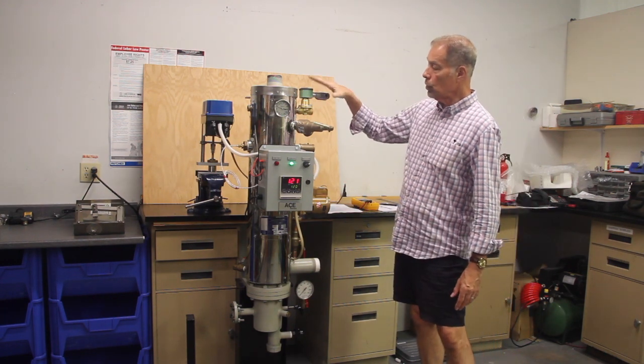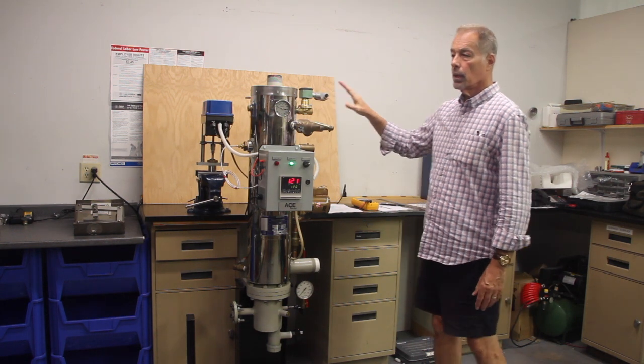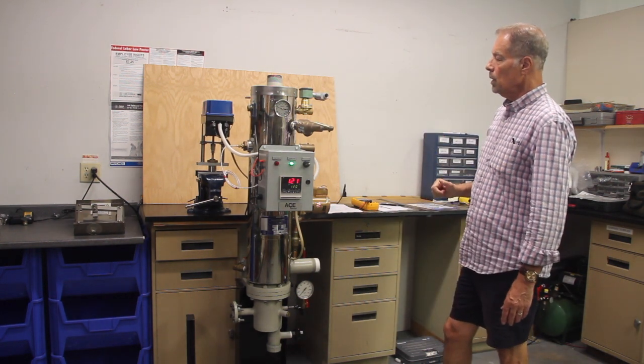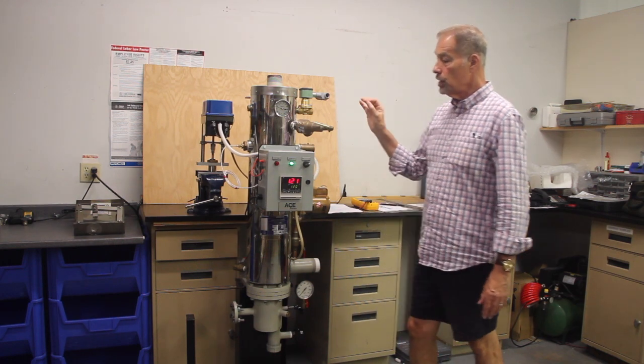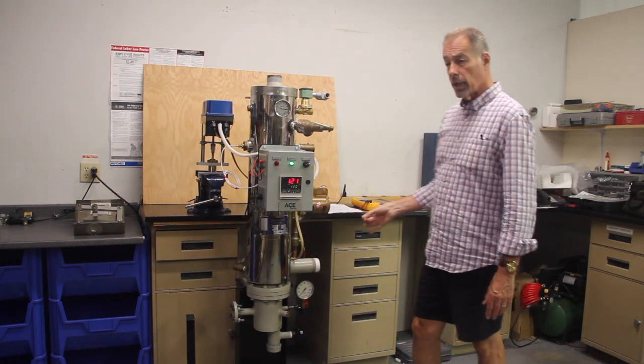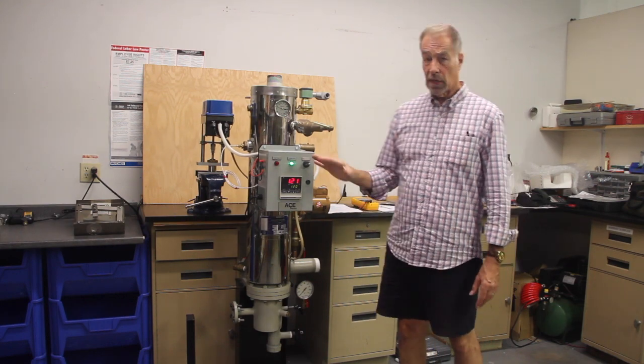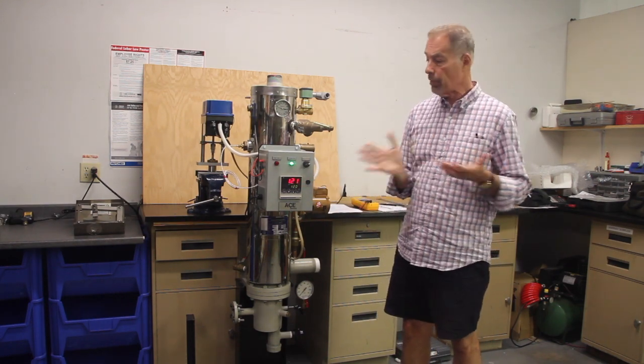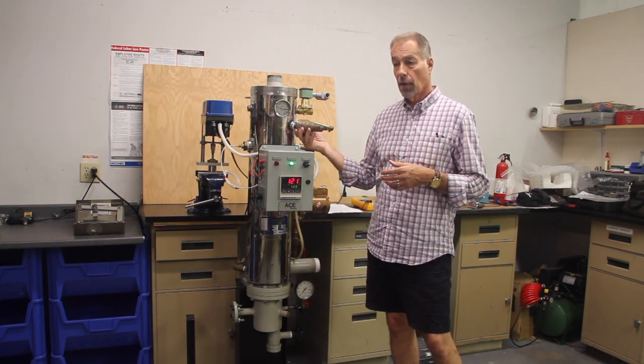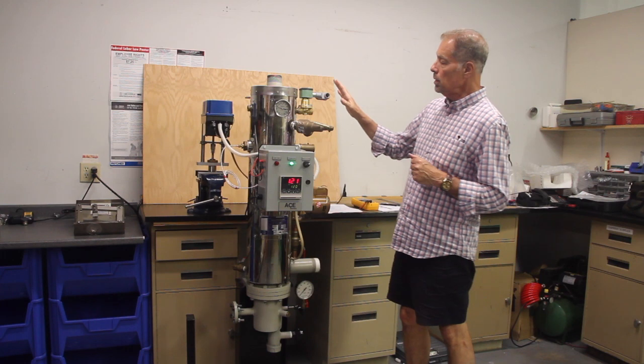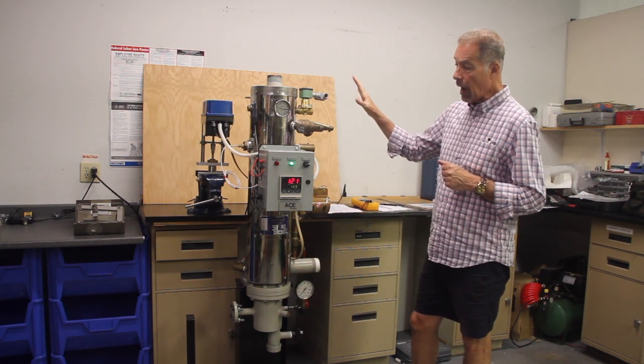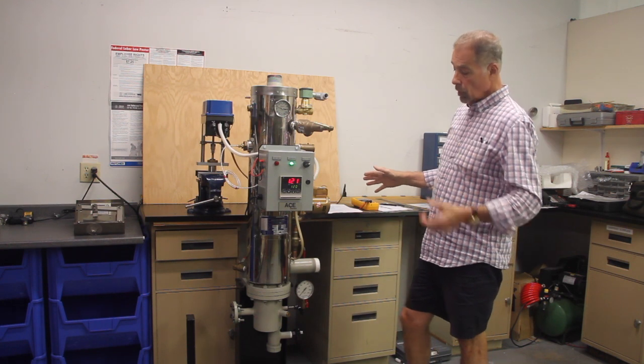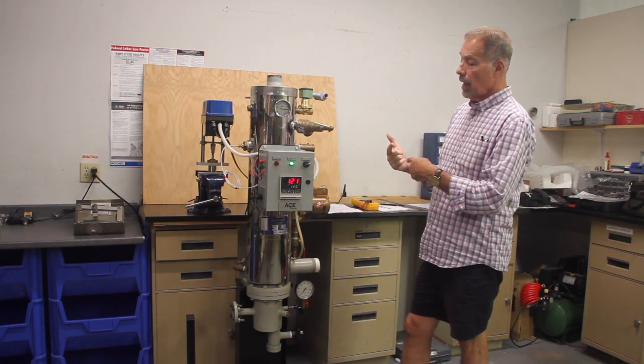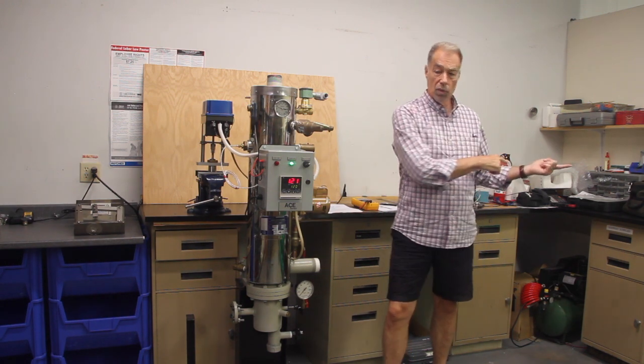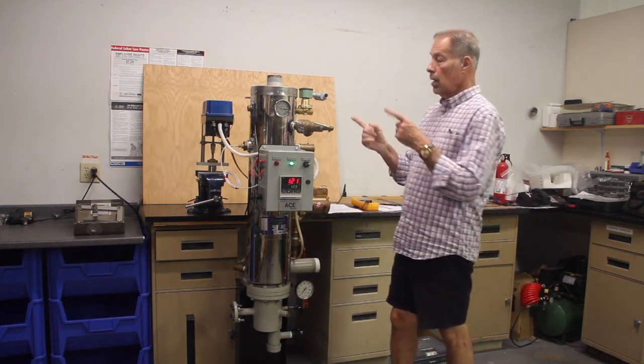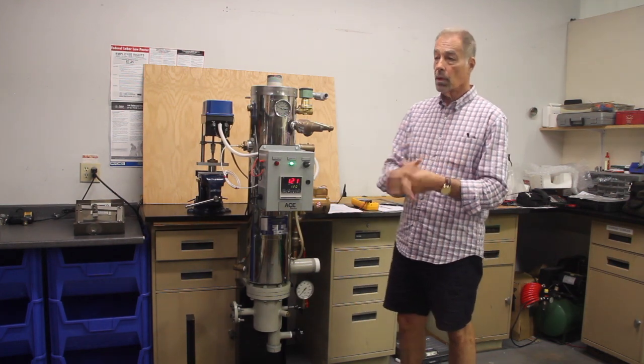What you're seeing here is a solenoid, an ASCO water solenoid. It's a two-way solenoid, and its job is to discharge the water into an indirect waste in the event something happens. The temperature control runs away. Something happens. We don't want the relief valve discharging if we can help it. We want to dump the hot water out of the heater. The cold water comes in, the heater resets, and then you get an annunciation at your building management computer saying, heater in building, the athletic center tripped, go check it out.